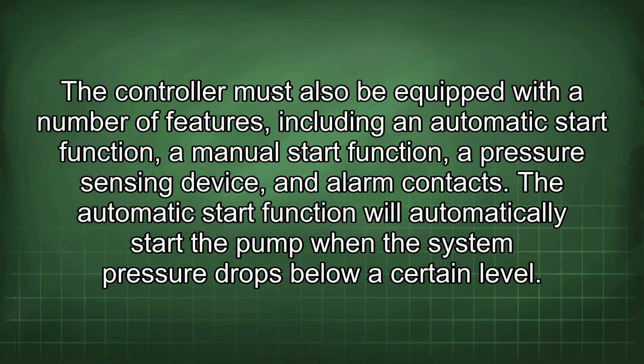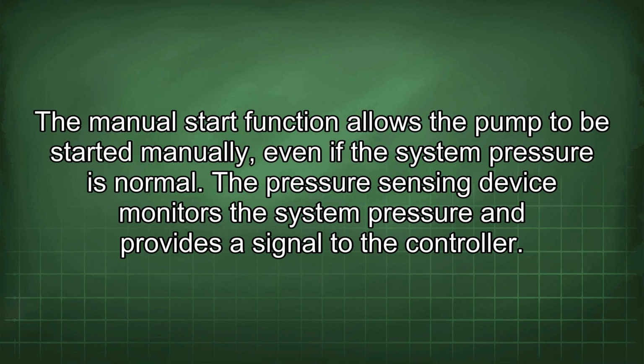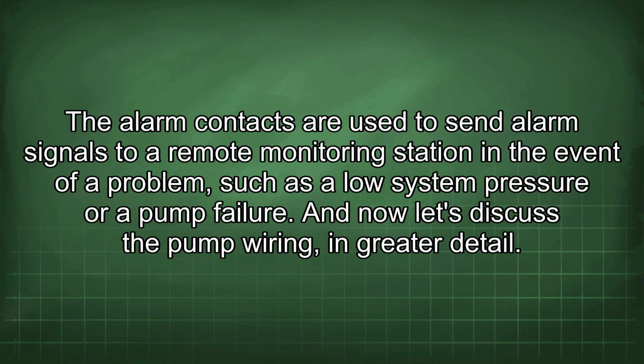The automatic start function will automatically start the pump when the system pressure drops below a certain level. The manual start function allows the pump to be started manually, even if the system pressure is normal. The pressure sensing device monitors the system pressure and provides a signal to the controller. The alarm contacts are used to send alarm signals to a remote monitoring station in the event of a problem, such as a low system pressure or a pump failure.